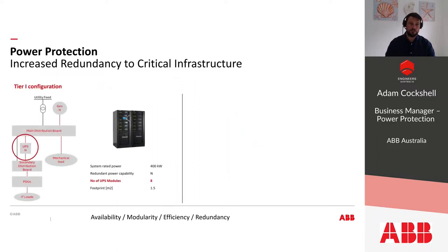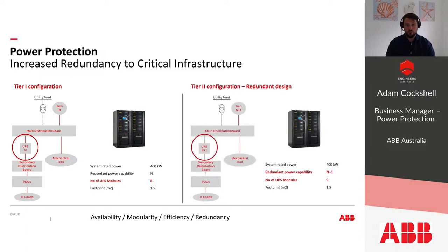What I'd also like to draw your attention to is how we can go from a tier 1 configuration into a tier 2 configuration without having any impact to the footprint of the UPS. So in this instance here, you can see that we've got a DPA 250S4 in parallel configuration with a system rated power output of 400 kilowatts. So in this instance, that's 4 modules in each one of those frames. So 400 kilowatt output. Without any increase to our footprint here, we've been able to go from a tier 1 design to a tier 2 design, including an N+1 in the system here.